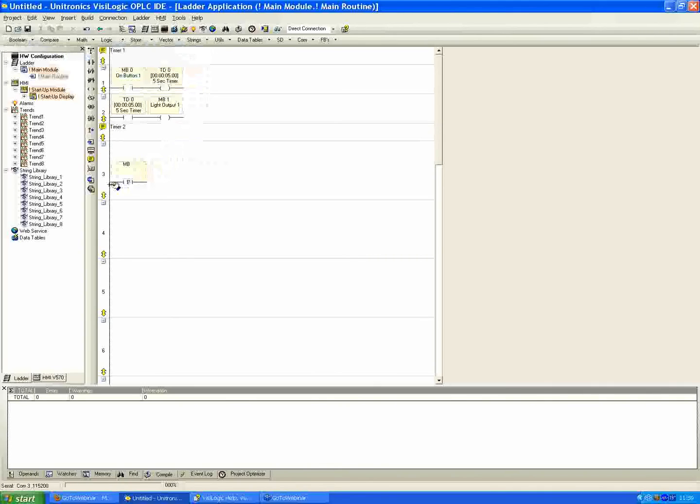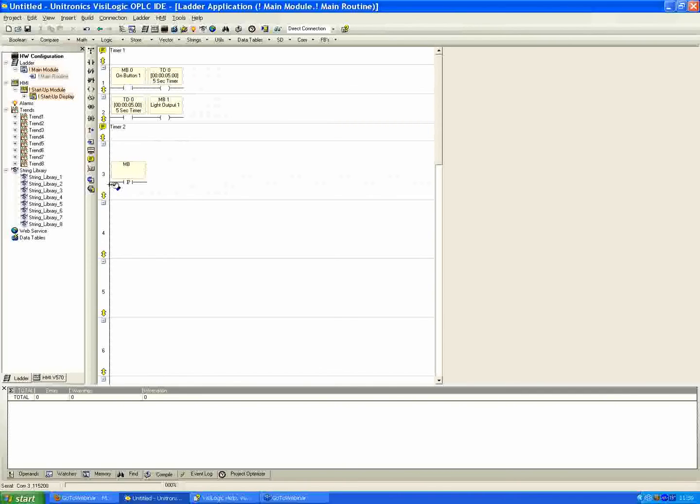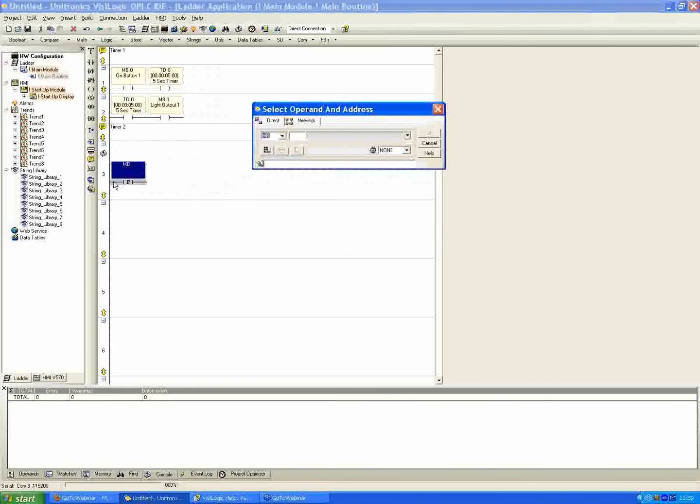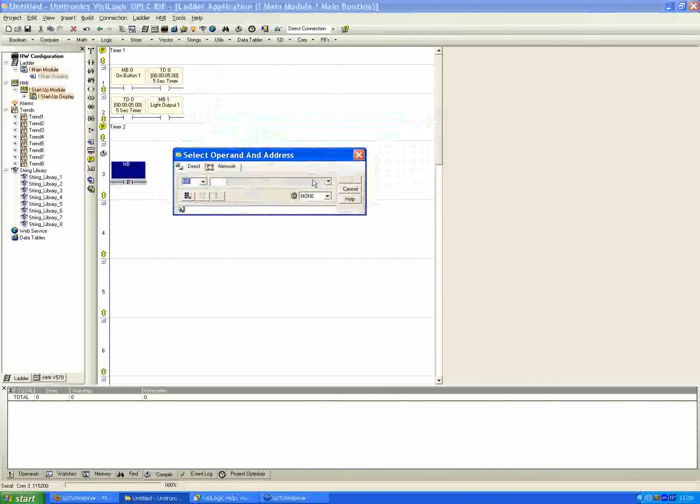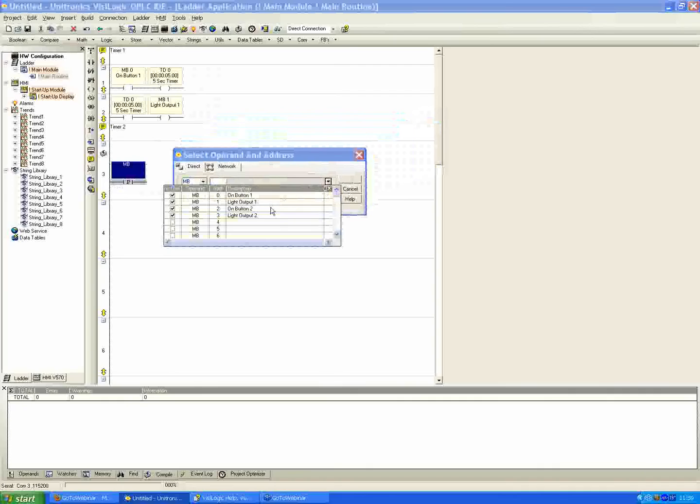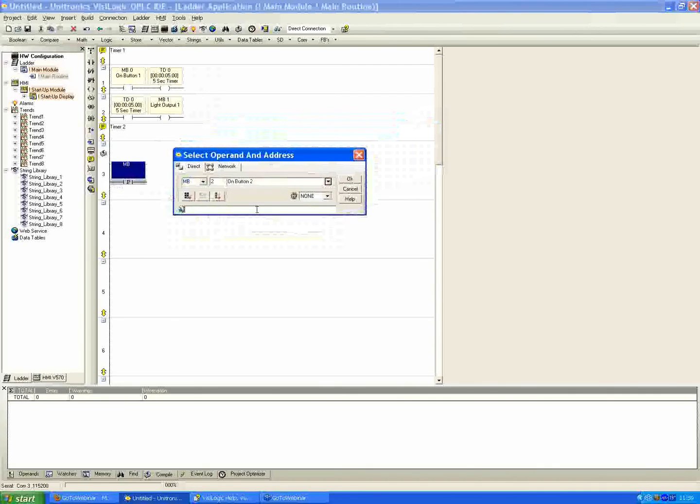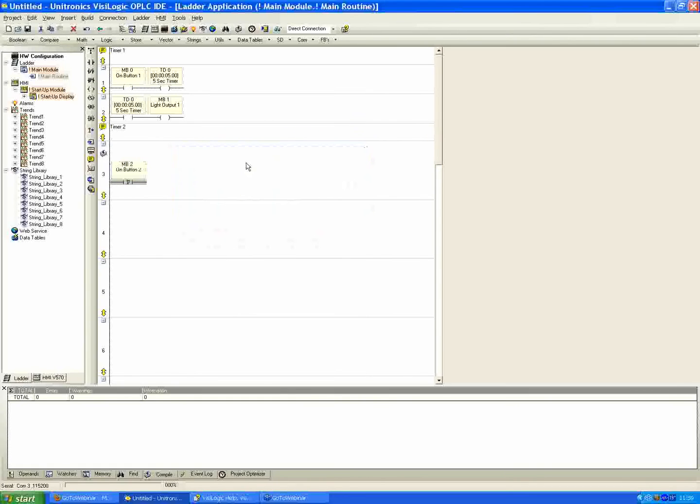So what this is going to do, basically, once we hit the button a single time, the contact here is going to recognize the rise of the bit associated, and it's going to only do that for the single scan. So I'm going to place that down. Again, I'll look on my drop-down list here, and I want to link it to my on button number two. And hit OK.